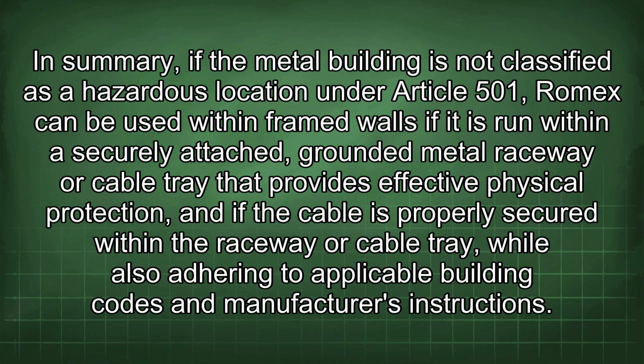In summary, if the metal building is not classified as a hazardous location under Article 501, Romex can be used within framed walls if it is run within a securely attached grounded metal raceway or cable tray that provides effective physical protection, and if the cable is properly secured within the raceway or cable tray, while also adhering to applicable building codes and manufacturer's instructions.